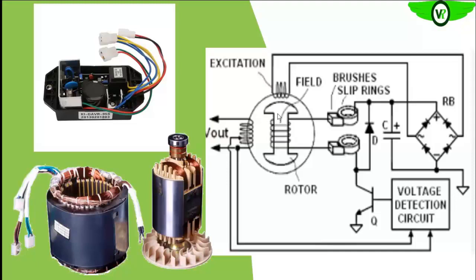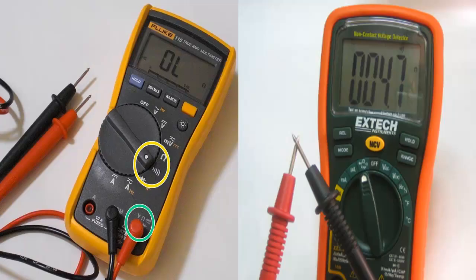The same magnetism that is produced in the main winding induces that excitation voltage into the excitation winding, and that is sent to the diode assembly in the AVR, okay? And that will be rectified, and then it will be regulated before it is sent to the main field. So this is the main field winding, as we said earlier, and this is the representation of the main field. Okay, so this is how you connect the AVR to your single phase generator.